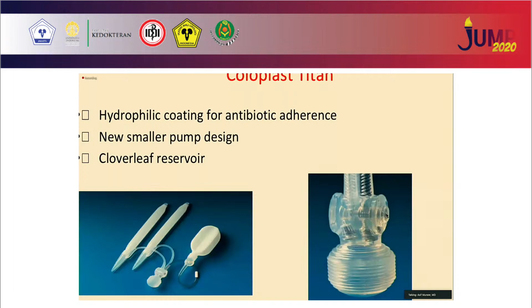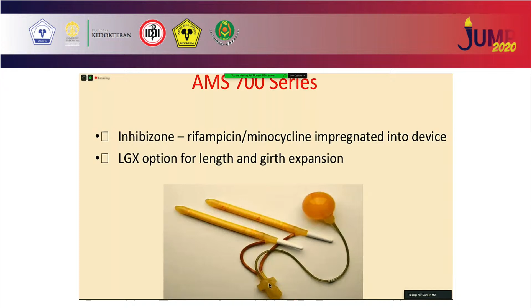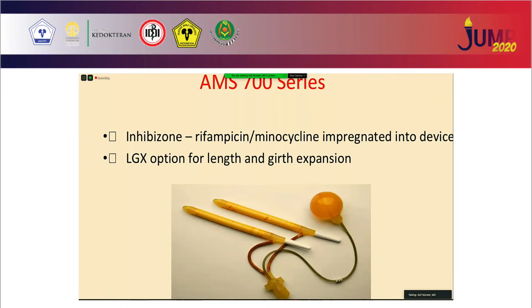This is an AMS 700. And again, it's been coated with InhibiZone over here, which is why it's a bit of a yellow color. Same principle, but the lockout valve is in the pump rather than near the reservoir. The cylinders on this one are a little bit softer as well. And if you've got people who've got either small length or narrow girth, the CXR version is very good for that because it's softer cylinders.